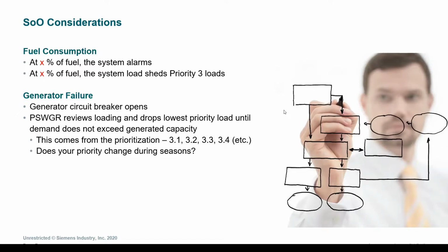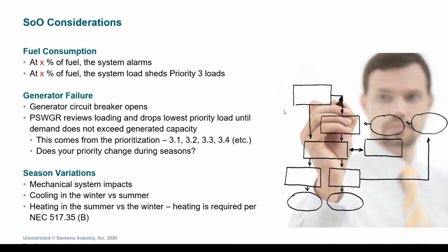One of the things we'll examine as well is how our priority changes as the seasons of the facility also change. It's important to understand and consider the fact that the mechanical systems region to region are different for the impact of the facility. Obviously, the cooling in the south is equally as important as the heating in the north. But we have to make sure we always design this in a code compliant manner, and that heating is required by code to be on the equipment branch.